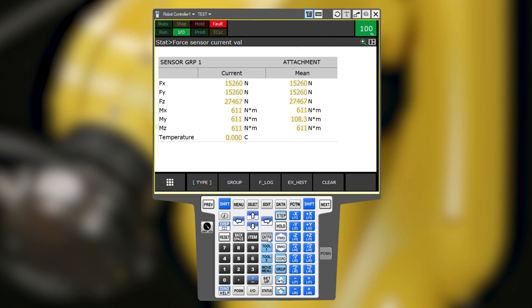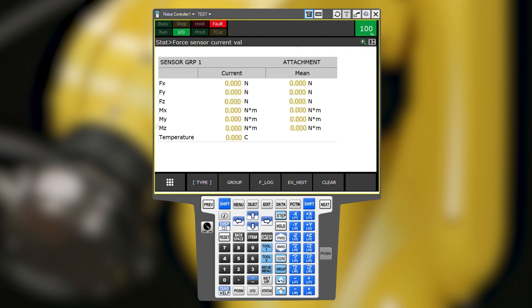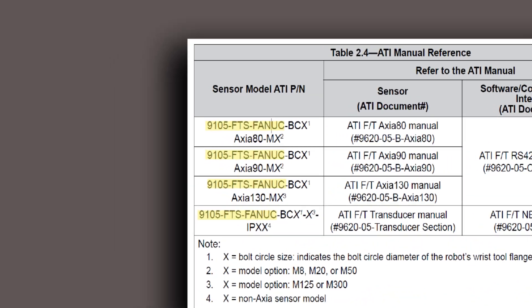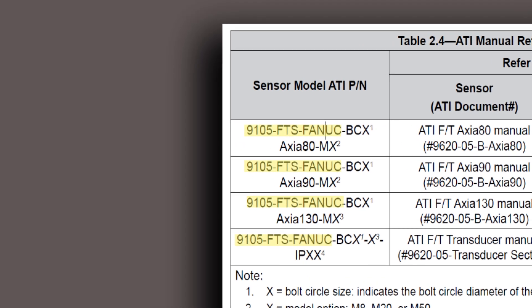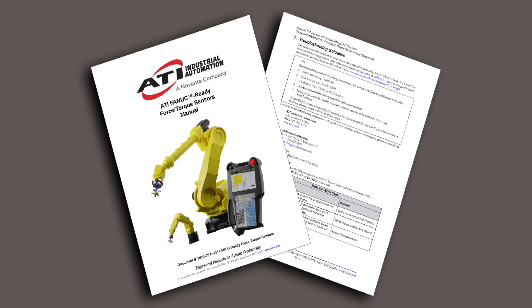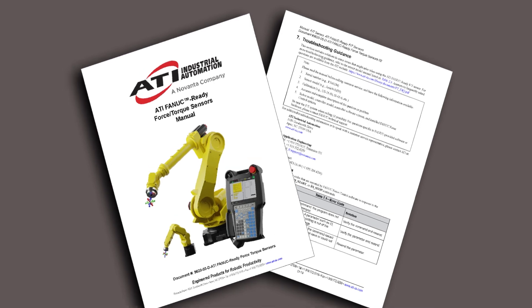If the values are all a static, very high number, the scaling factors may not be being read off of the sensor properly. If you see this behavior, or if the values remain all zero after several power cycle attempts, confirm that your sensor is indeed a FANUC-ready ATI sensor. Refer to troubleshooting documentation or contact ATI support.